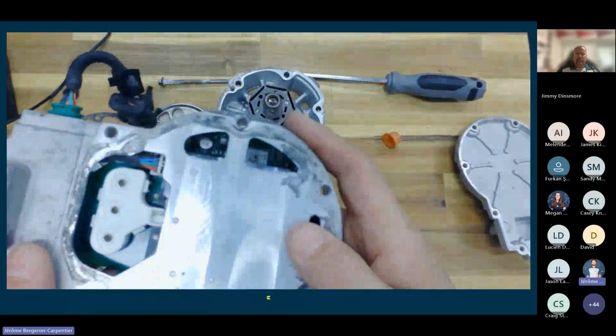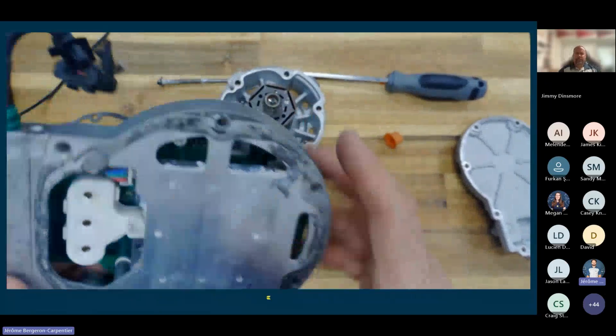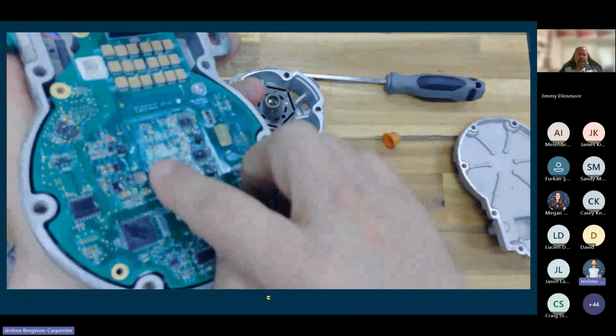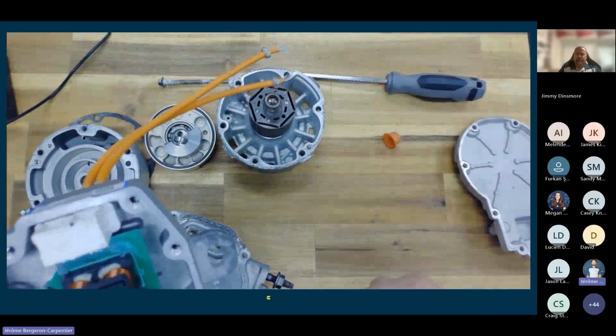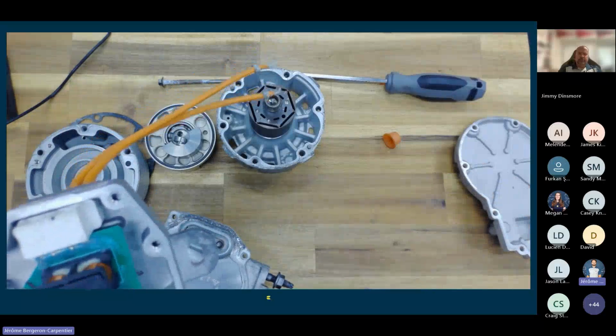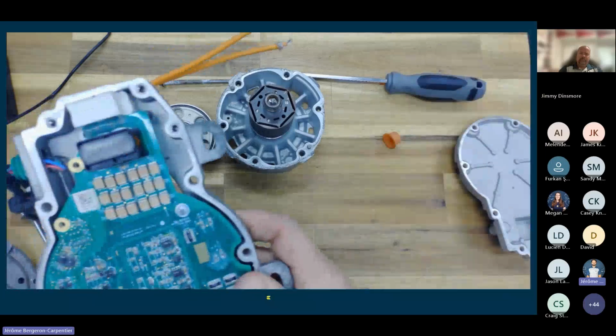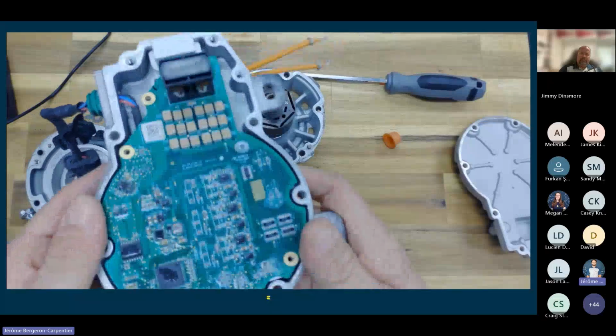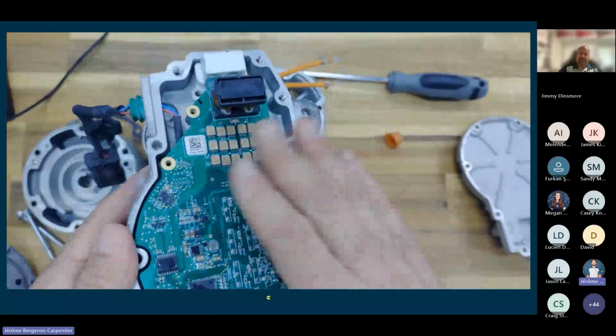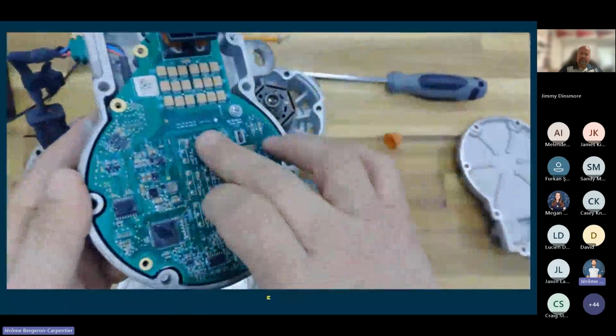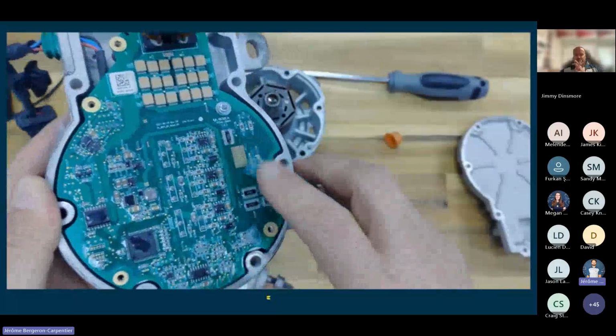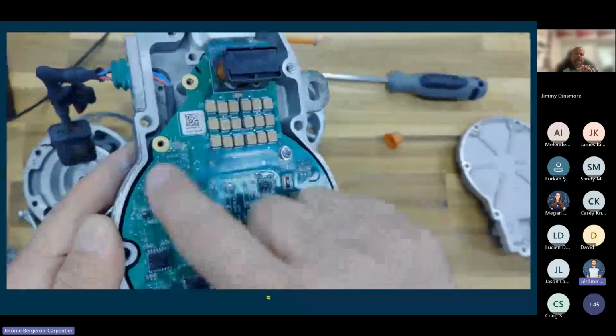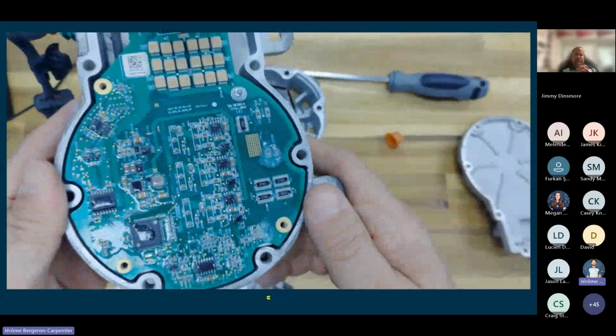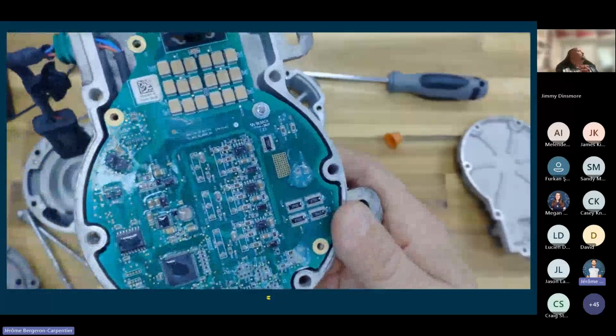And as you can see, there are actually capacitors inside the unit itself. And this one's cold soldered right to the board, or soldered to another board underneath here. And that's why when we were testing with the vehicle, doing the isolation test, we had reserve energy after I did an isolation test, because I didn't let the capacitors discharge by using the proper function of that tool. And they're pretty much all the same. I have several different types of isolation testers there. So inside here, we have our IGBTs that actually control our 3-phase. We have our control side, pulse width modulation on them. We have our high voltage components. We have our CAN bus communication on here, and of course our electronics for our function and strategies and so on, part of the unit itself.